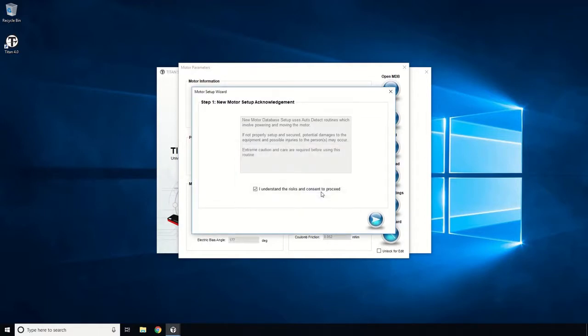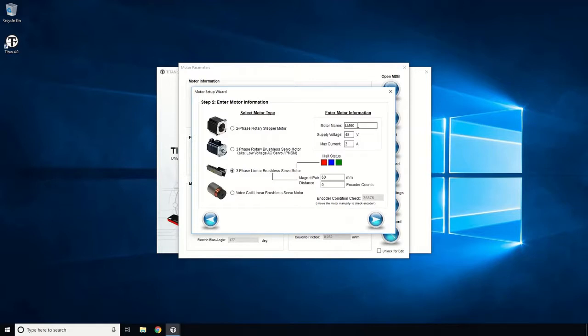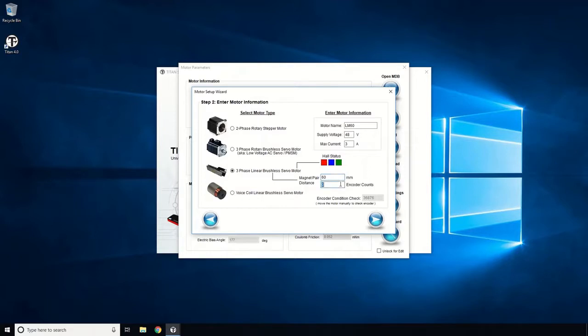Select 3-phase linear brushless servo motor. Enter the motor name, the voltage, and the max current to use for this motor. In this example, we will name the motor LM60 and enter 48 volts and 3 amps. Next, we will enter the magnet pole pair distance as 60 mm.